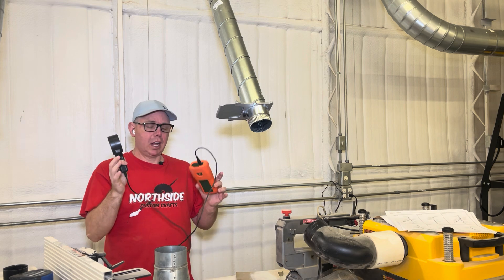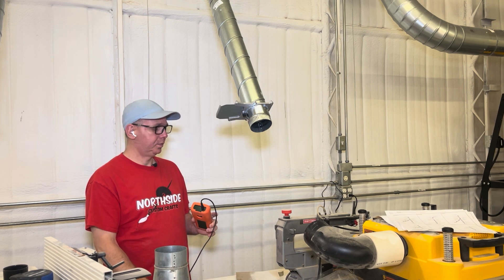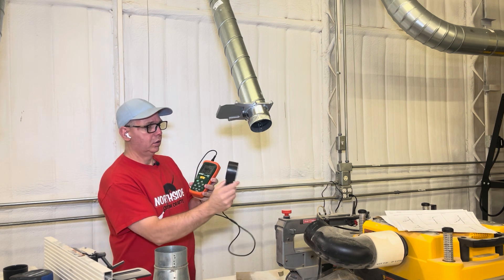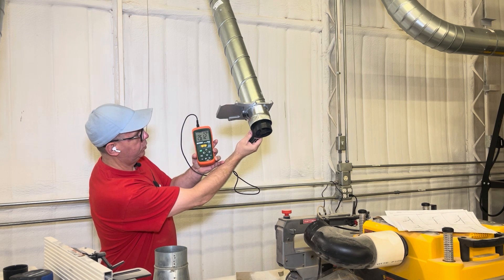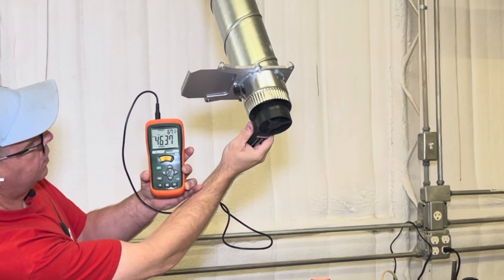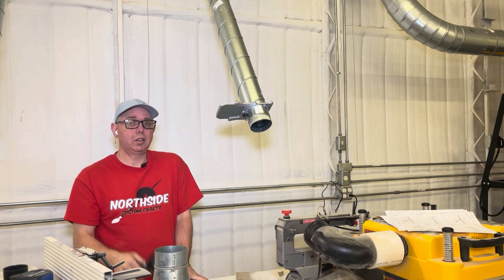If you have a hundred air leaks like that, it's like having a few blast gates open. This is the closest blast gate, and this anemometer is calibrated for four-inch pipes. Let's call it 460 CFM. Now let's go to the furthest one.